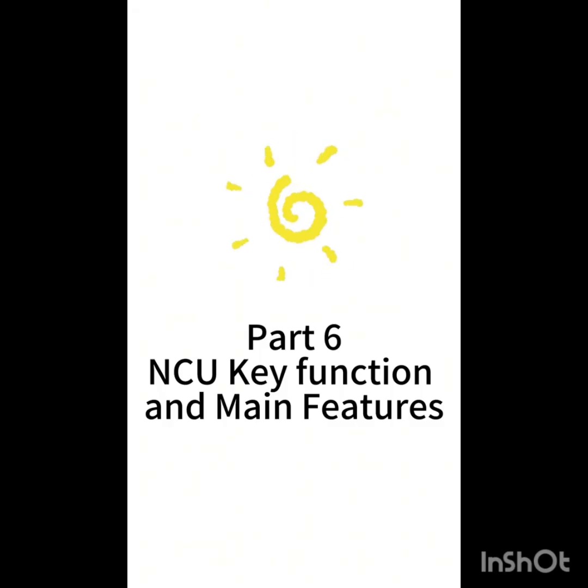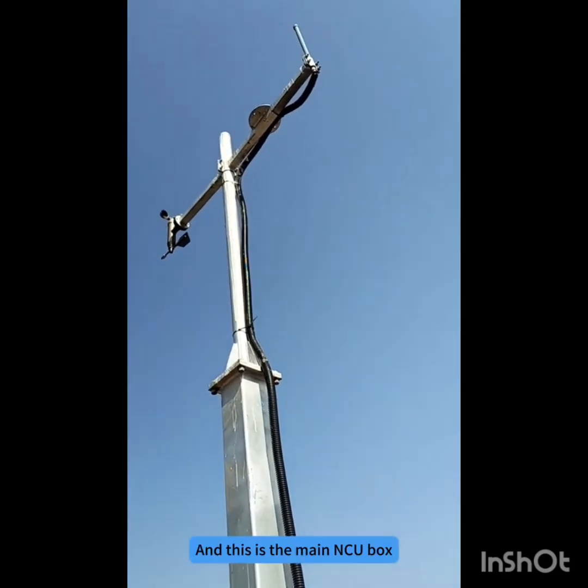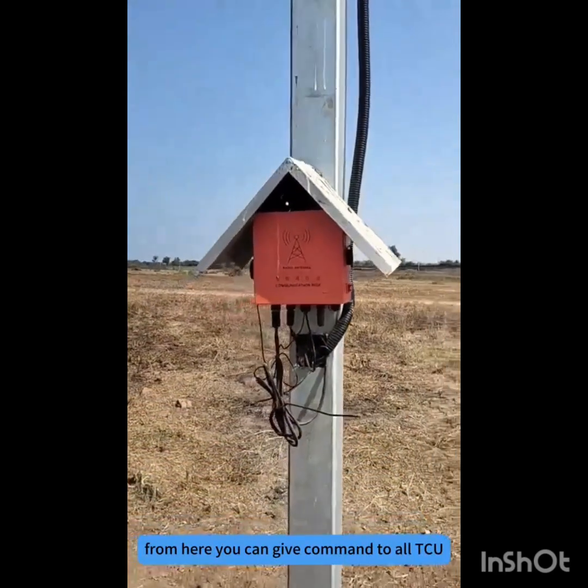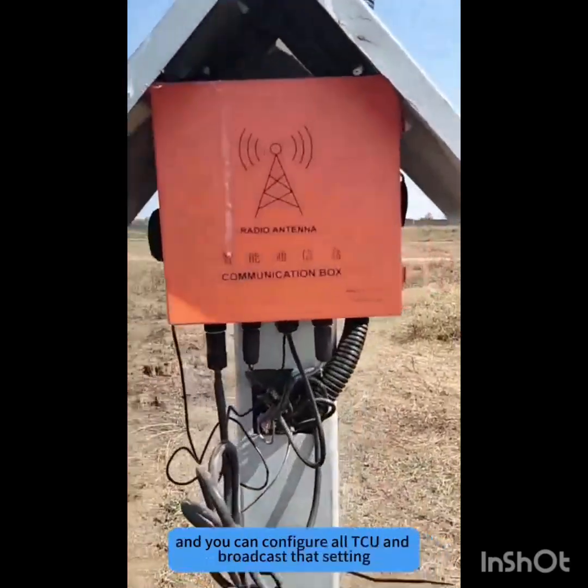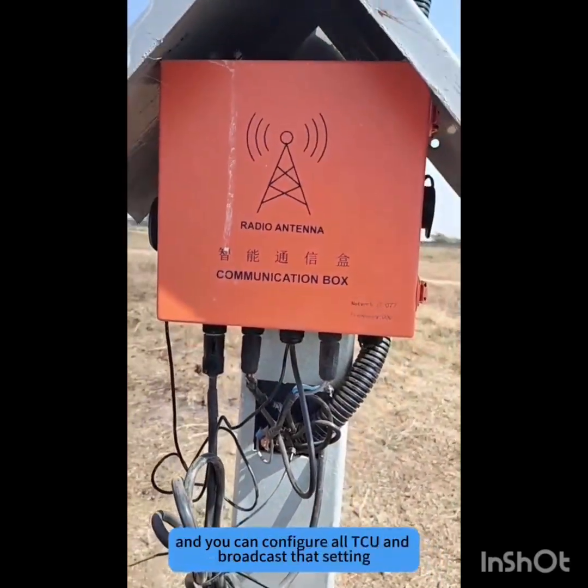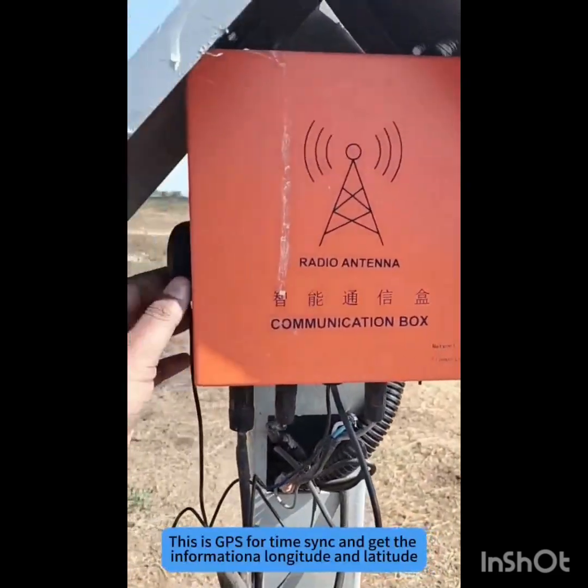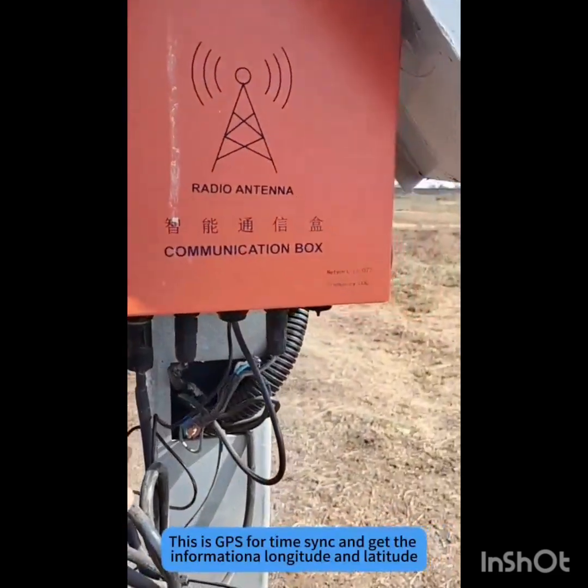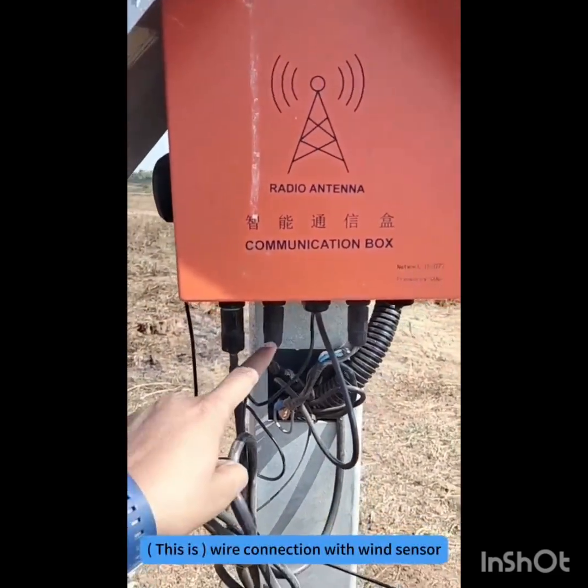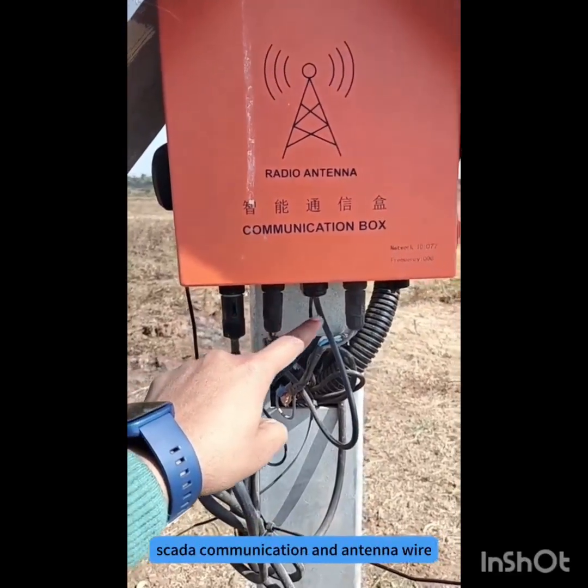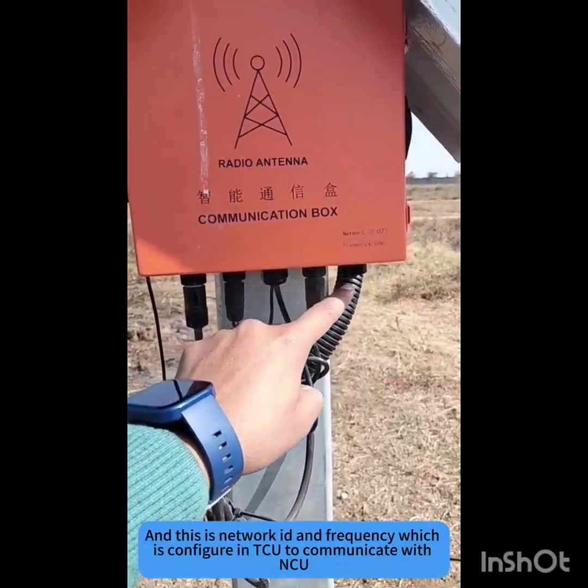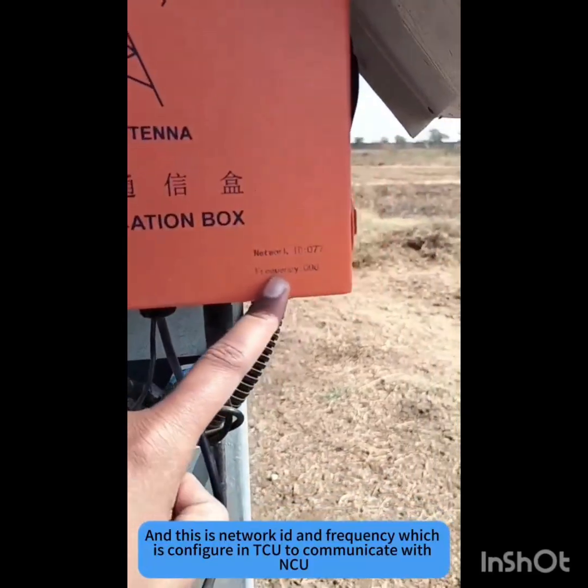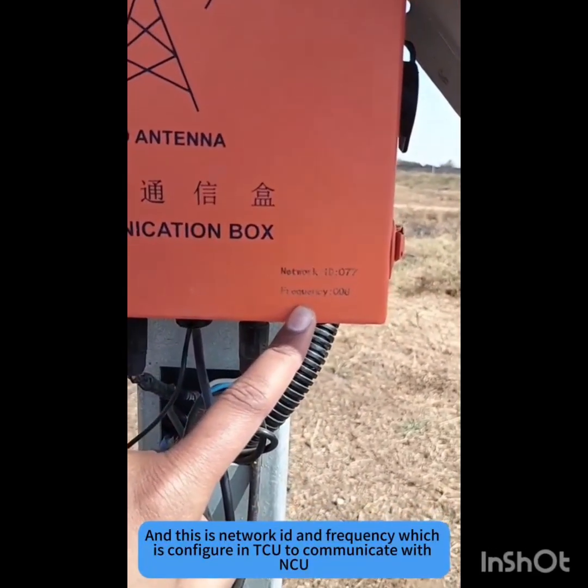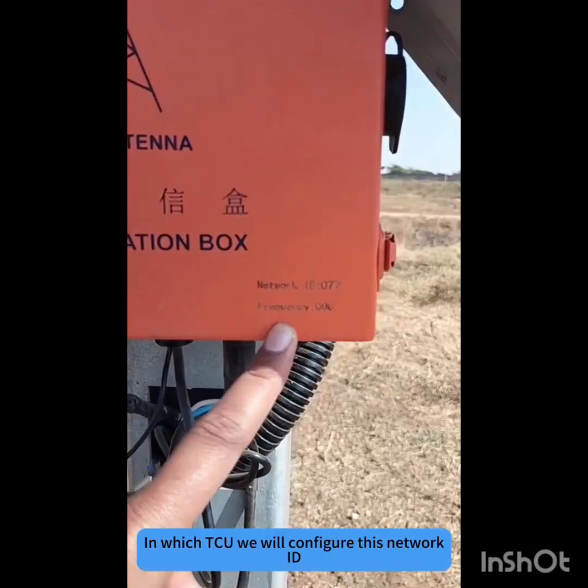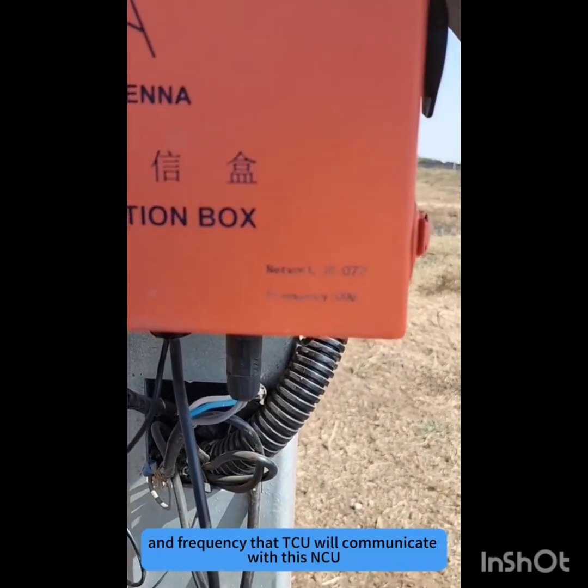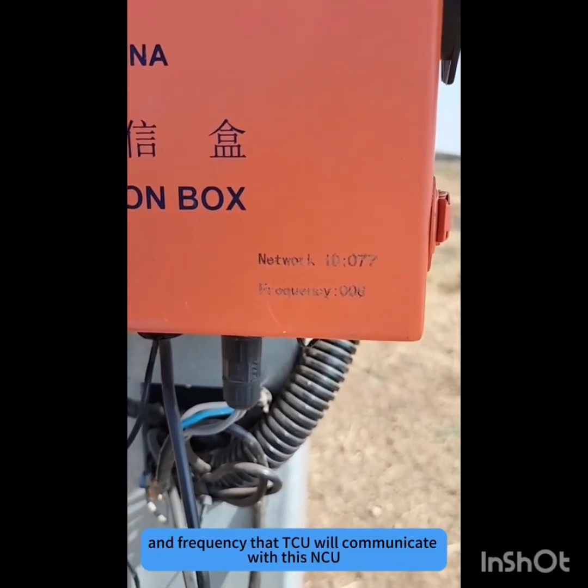Part 6. NCU key functions and main features. And this is the main NCU box. From here you can give commands to all TCUs, configure all TCUs and broadcast that setting. This is the GPS for time, to get the information of longitude and latitude. The connections are: wind sensor, SCADA communication and antenna, power, and this is the network ID and frequency which is configured in the TCU to communicate with the NCU. In whichever TCU we configure this network ID and frequency, that TCU will communicate with this NCU.